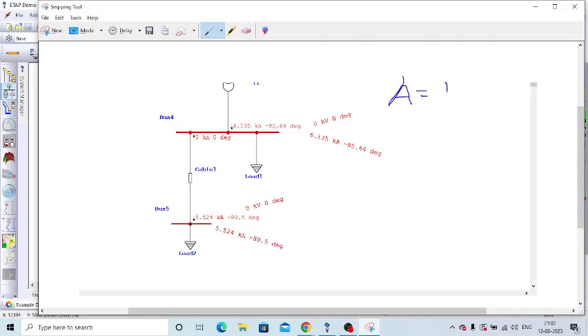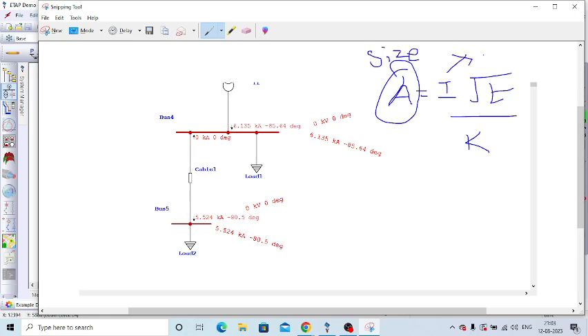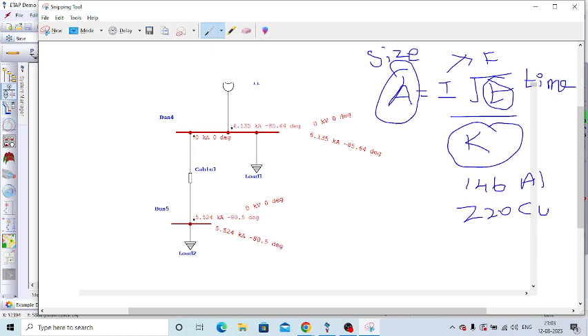So A equal to I into root T divided by K. So A means the square size of the cable. A is the size of the cable. So this is for the short circuit current calculation. So I is fault current. T is time, that is the breaker operating time. Then K is a constant. So for K, I remember 146 for aluminum cable, and 220 for copper cable, I remember. So based on this formula, we have to arrive at this size.